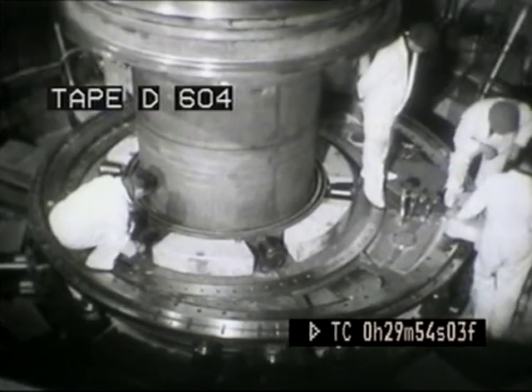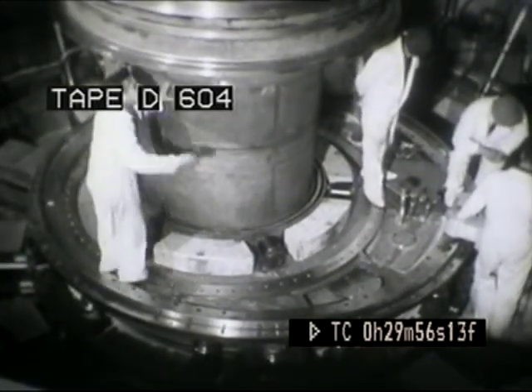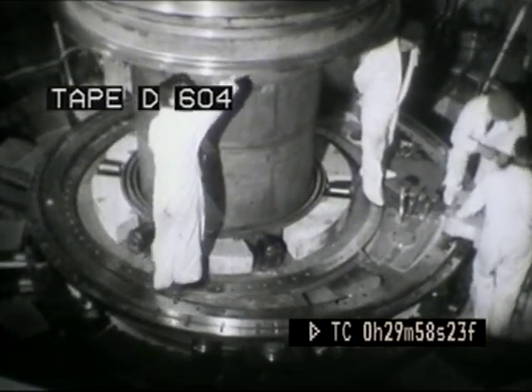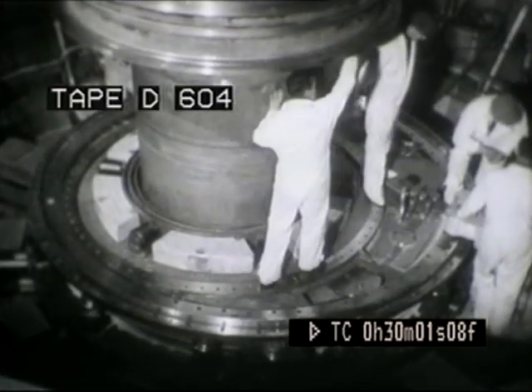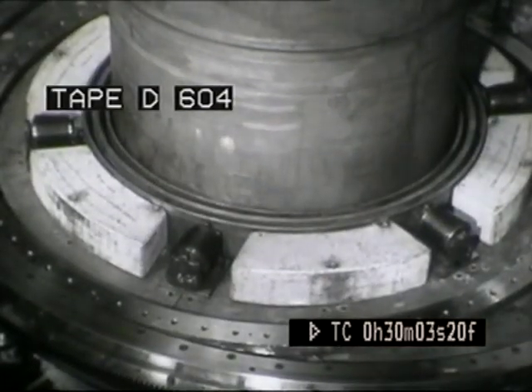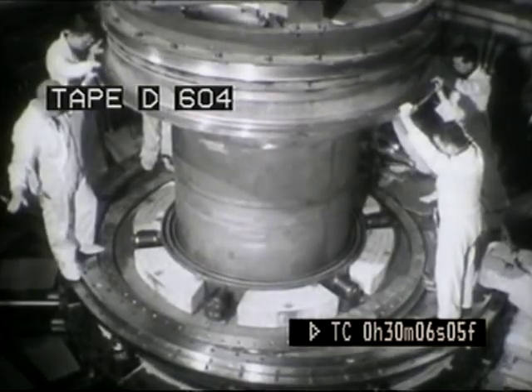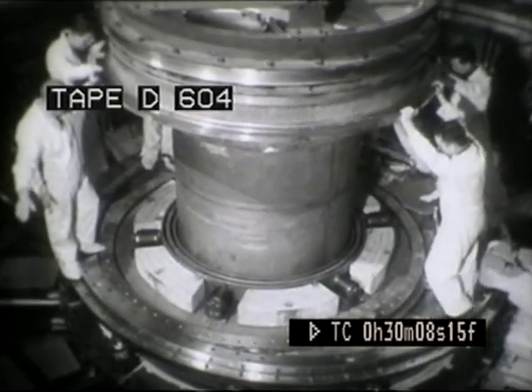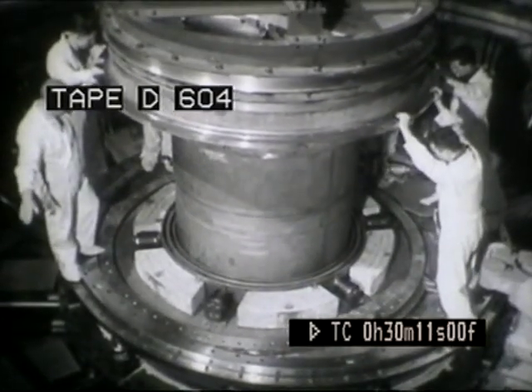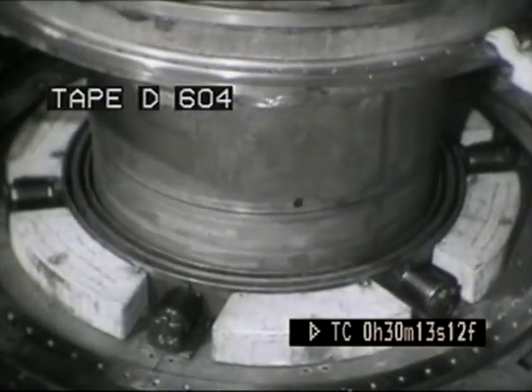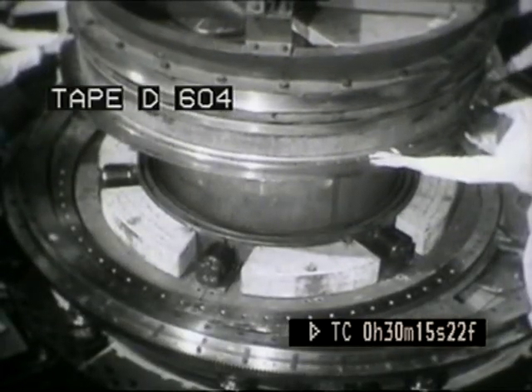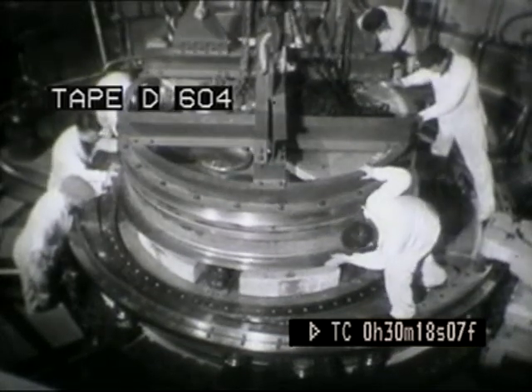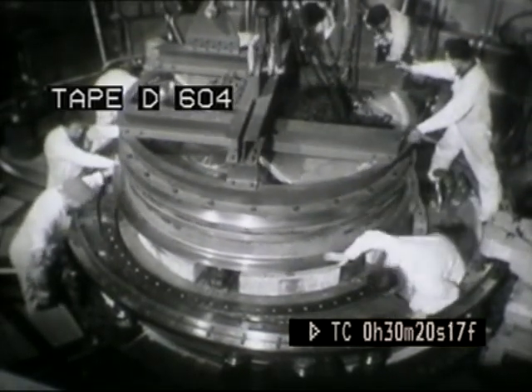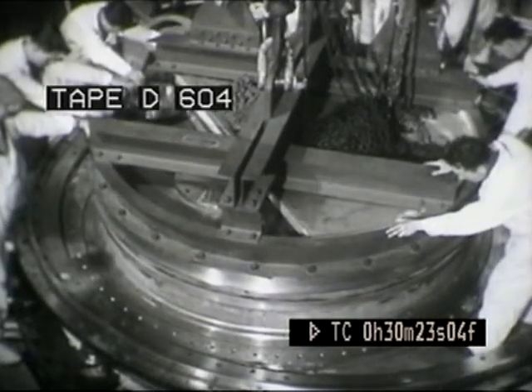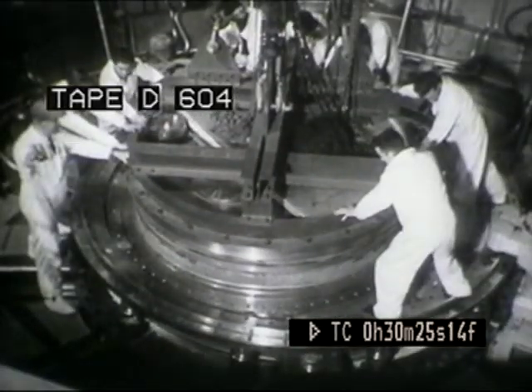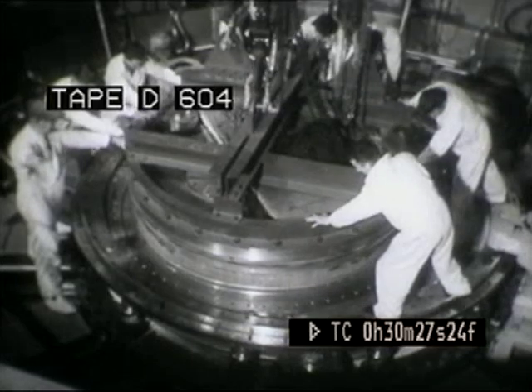The inner shield was then lowered into the hole, set eccentrically in the outer shield, and was supported by roller bearings set around the top. Similar skirts were fitted between the rotating shields to maintain the necessary seal. During the operation of the reactor, both shields will be raised off their rollers by jacking mechanisms and bolted up to flanges to form high-pressure gas seals.